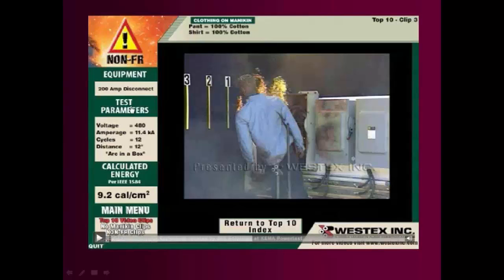Well, let's look at the label over here to the left. See where it says equipment? That's a 200 amp disconnect. If you go down to test parameters, you see that the voltage is 480 volt. The available short circuit current is 11.4 kA. What does that mean? That's 11,400 amps. The cycles are 12 cycles. Well, what is that all about? Well, we have in this country a 60 hertz system, which means 60 cycles in 1 second. So in 12 cycles, less than a second, at a distance of 12 inches, this is the kind of damage that can happen on a 200 amp disconnect at 480 volt.